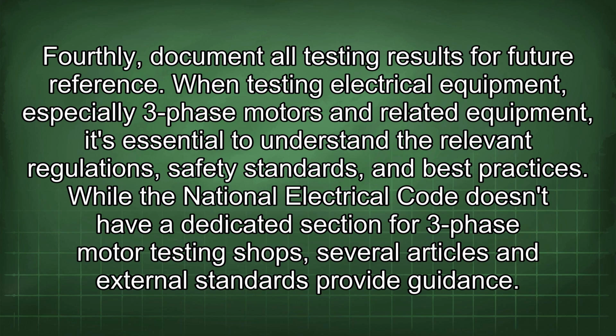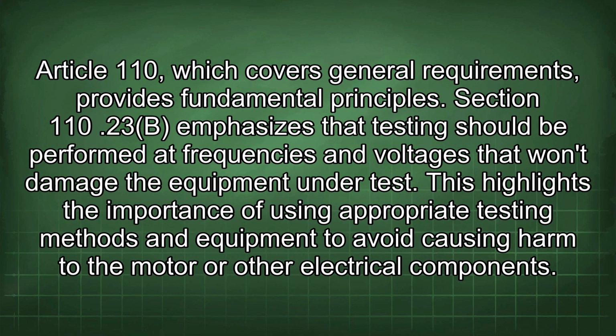When testing electrical equipment, especially three-phase motors and related equipment, it's essential to understand the relevant regulations, safety standards, and best practices. While the National Electrical Code doesn't have a dedicated section for three-phase motor testing shops, several articles and external standards provide guidance. Article 110, which covers general requirements, provides fundamental principles. Section 110(23)b emphasizes that testing should be performed at frequencies and voltages that won't damage the equipment under test.